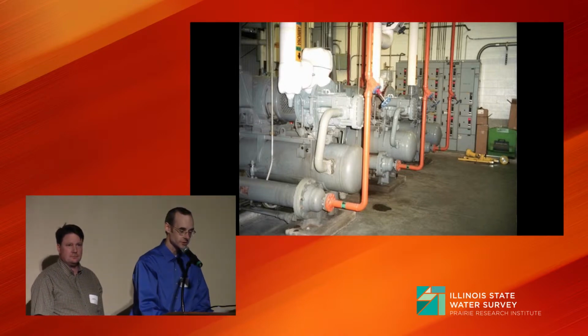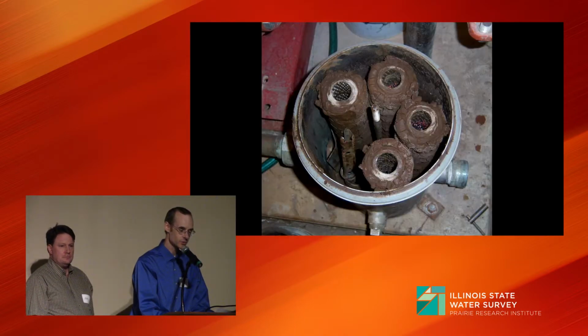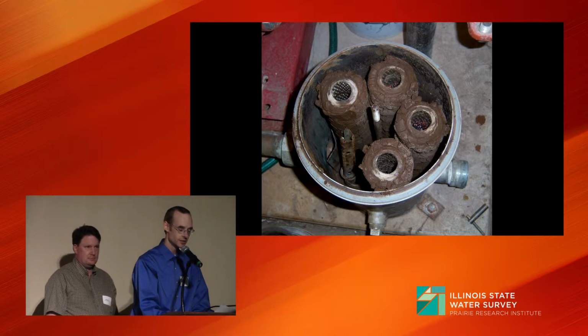Corrosion is a primary concern. This is a filter on a system with corrosion problems. An unprotected system can corrode 10 to 20 times as fast as one with adequate protection, which is provided by good water treatment. For example, 100 feet of 12-inch steel pipe that corrodes at a rate of 5 thousandths of an inch per year loses 64 pounds of metal and produces 2.6 cubic feet of rust every year. That's as much rust as a medium-sized dog.